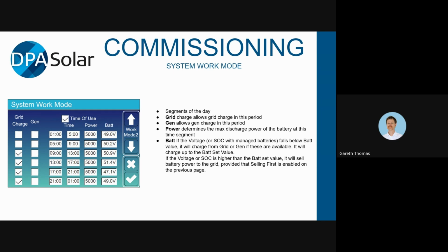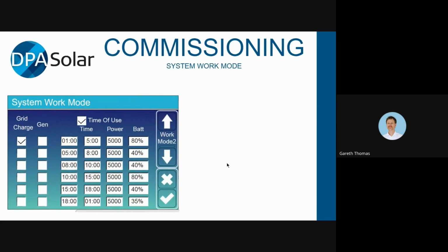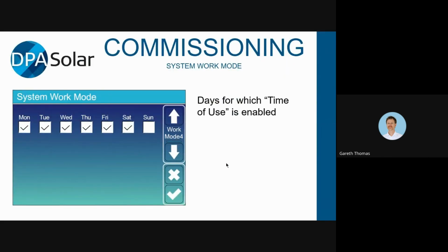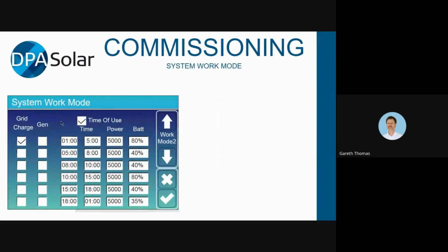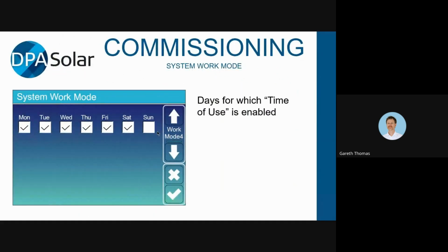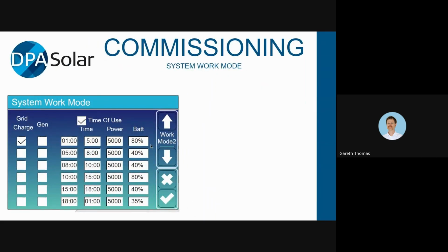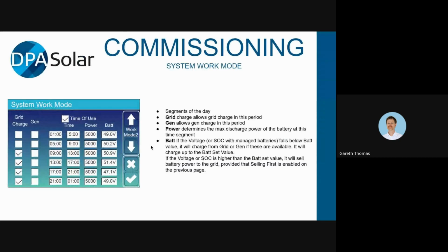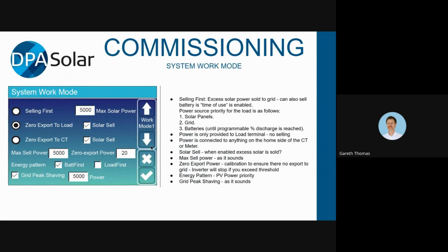And so I sell to the grid in the evening, and I manage it from this little menu here. And then the third page after this is system work mode, and it just has these days for which the time of use is enabled. So you can have everything set up in this menu here, but say on Sunday, it won't use that. And if you don't have time of use enabled, it's just going to behave according to the standard values that you've got set up in your battery charge settings.